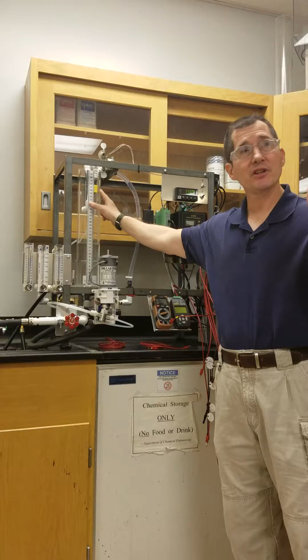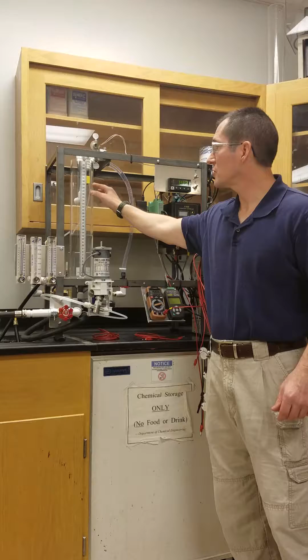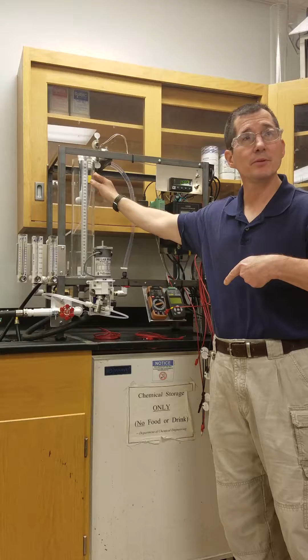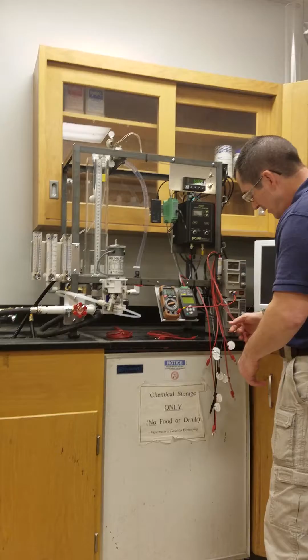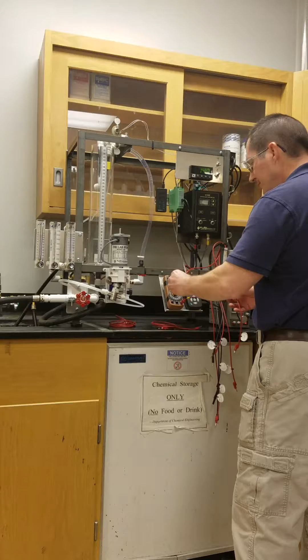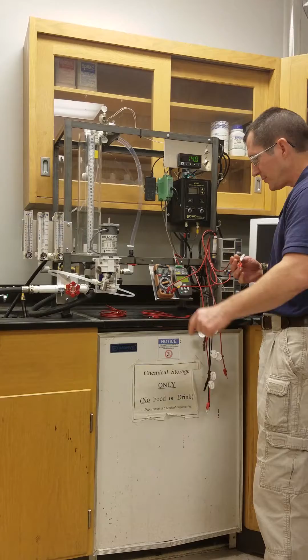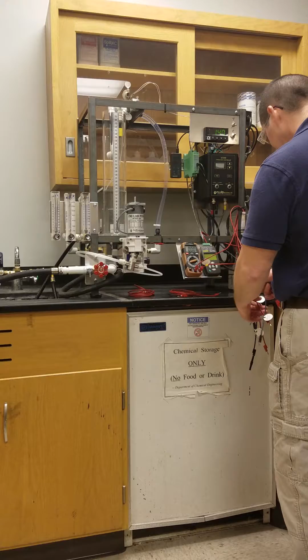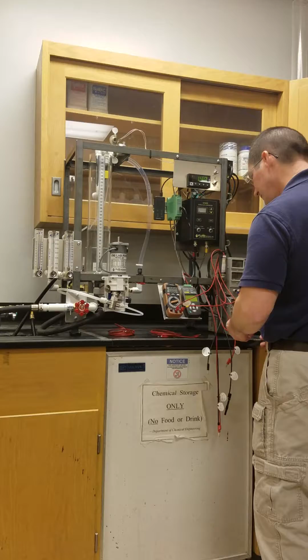Basically it's like a little relay inside there. As long as this float is down, the connection is closed and you can get current flowing through it. If the water level gets too high, this float will move up, and when it moves up, it cuts off the electrical signal going to the pump. So it's a safety device. So I have to go through the level switch. So here we go. Level switch, level switch. It's kind of a pass through. So I'm going to run the control signal through the level switch. It comes out of the level switch, and then it needs to go to the control valve. CV signal here.